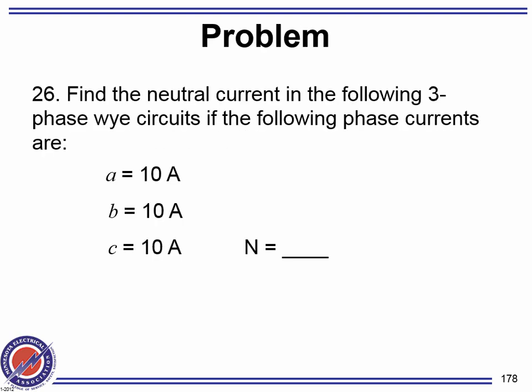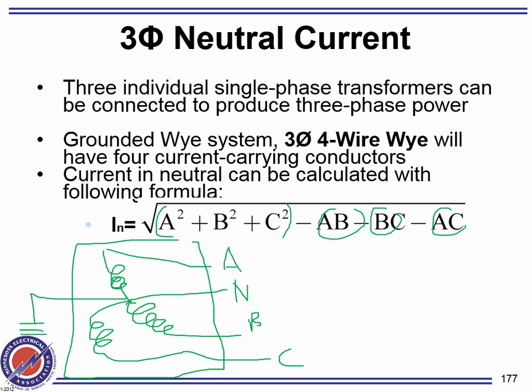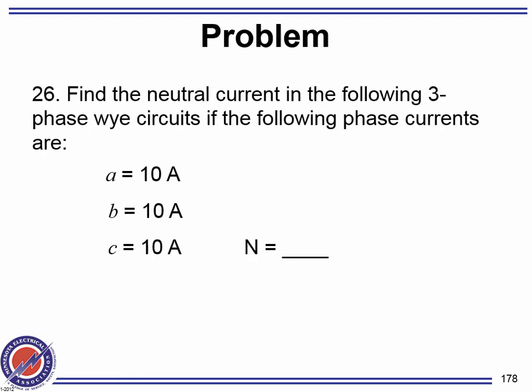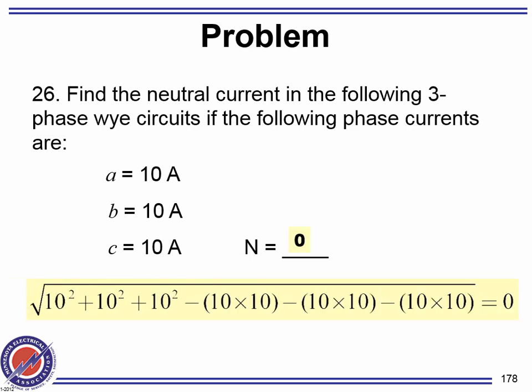All right, let's take this. Now remember, what happens if this is carrying 10 amps and this is carrying 10 amps and this is carrying 10 amps, how much would the neutral be carrying? Zero. So that's a balanced three-phase system. That's the beauty of the three-phase system. If all of them are carrying the same and there is no harmonics, remember there's something called harmonics, zero. If you don't believe it, plug in all the numbers and that will get you zero.